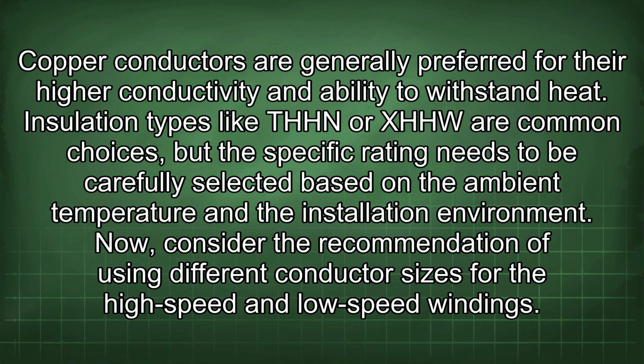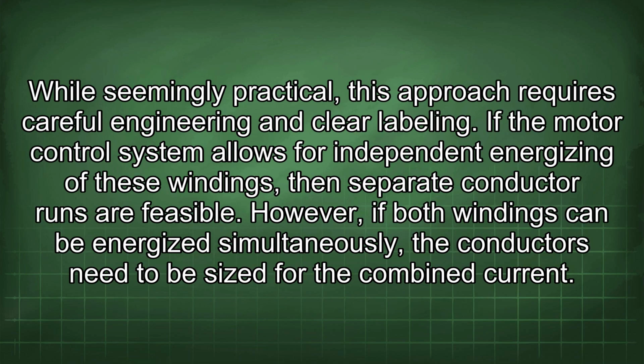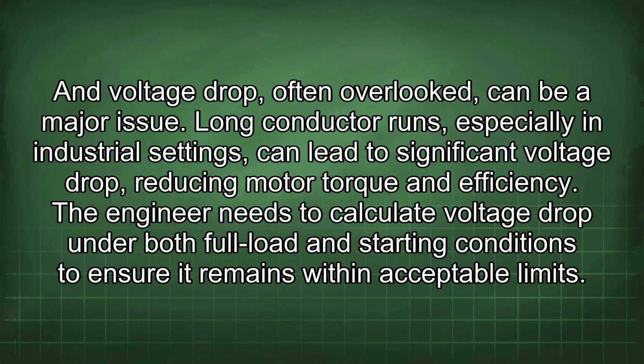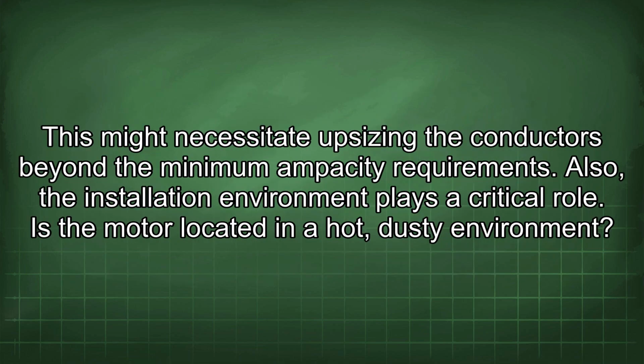Now consider the recommendation of using different conductor sizes for the high-speed and low-speed windings. While seemingly practical, this approach requires careful engineering and clear labeling. If the motor control system allows for independent energizing of these windings, then separate conductor runs are feasible. However, if both windings can be energized simultaneously, the conductors need to be sized for the combined current, and voltage drop, often overlooked, can be a major issue. Long conductor runs, especially in industrial settings, can lead to significant voltage drop, reducing motor torque and efficiency. The engineer needs to calculate voltage drop under both full load and starting conditions to ensure it remains within acceptable limits. This might necessitate upsizing the conductors beyond the minimum ampacity requirements.